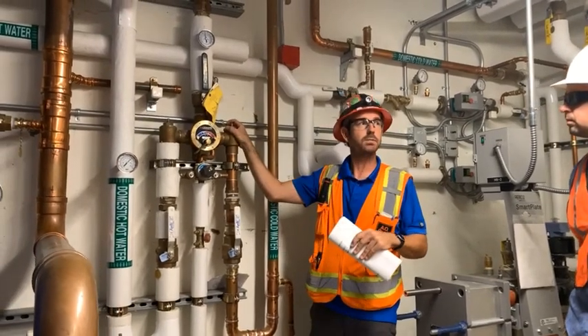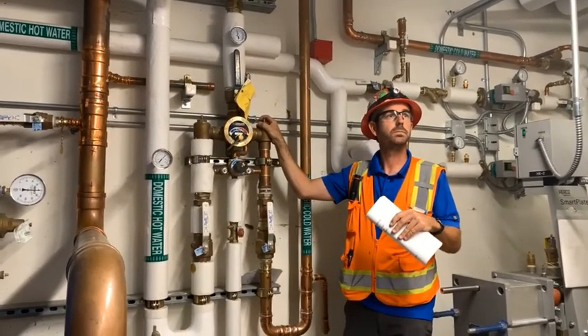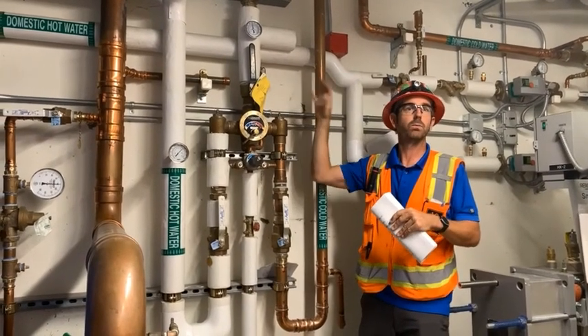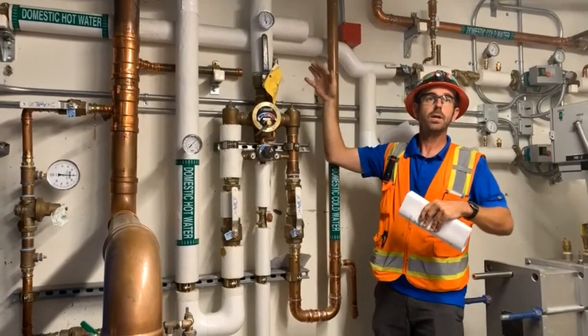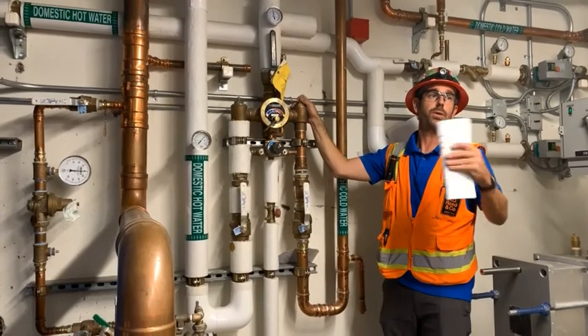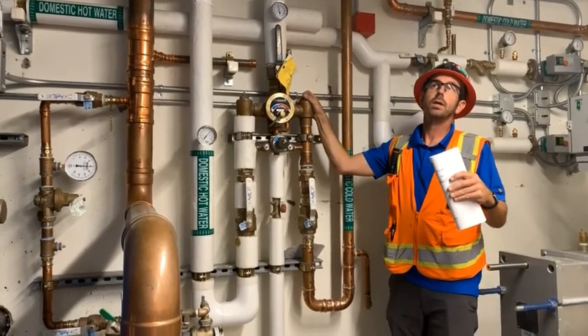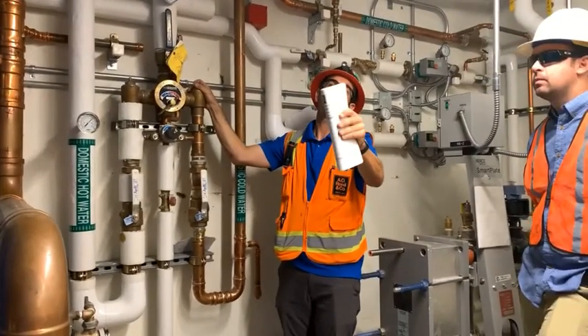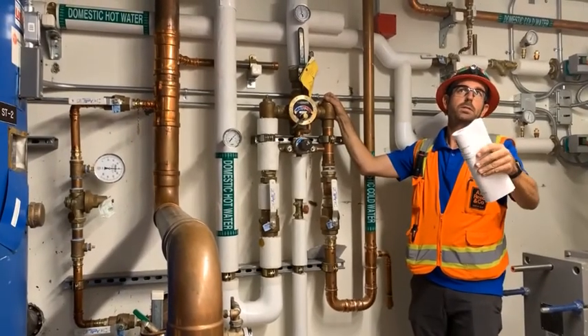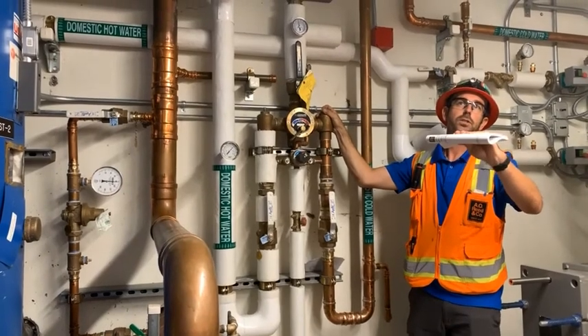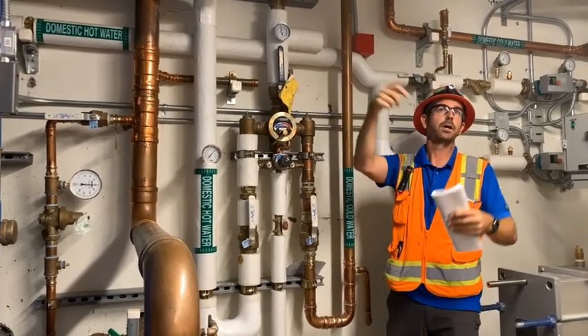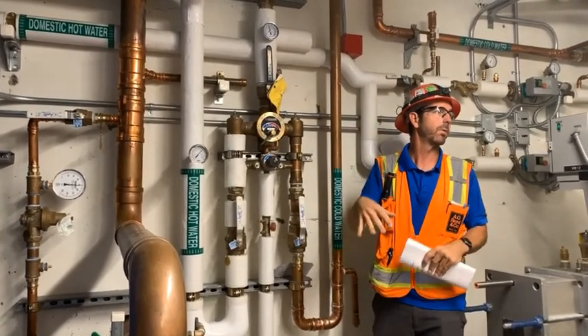You guys have any questions on this mixing valve, how it works? Do you get the idea? We want 120 always leaving this thing. So if you did need to do a shutdown and you need to bring the system back online, on each pump there's a hose bib. Probably the easiest way would be to shut the power to the pumps off and run a hose, and you just gotta dump a little bit of water down the drain.